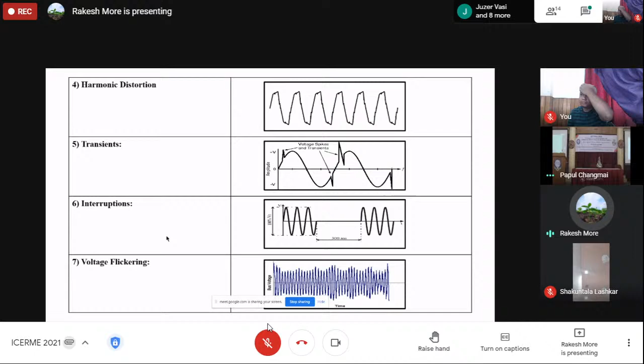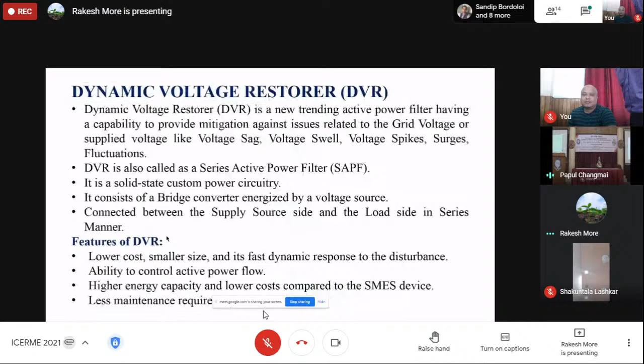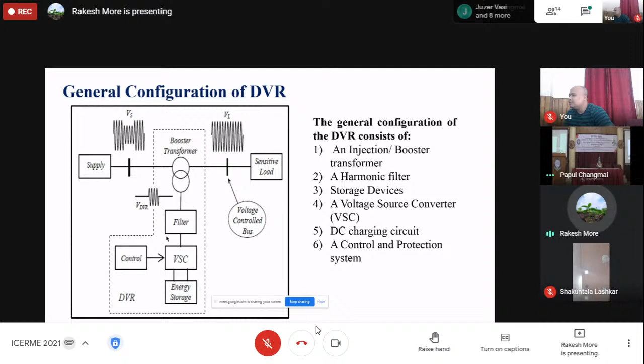For overcoming or mitigating this issue, I implement a dynamic voltage restorer. For energizing the dynamic voltage restorer, we require a separate DC supply and also a control circuit. The DVR consists of one 3-leg bridge inverter, which has a DC energizing source. This 3-leg converter injects the voltage through a series transformer in the transmission line, which provides the compensation for all these power quality issues. For energizing the DVR, I implement here the solar panel.